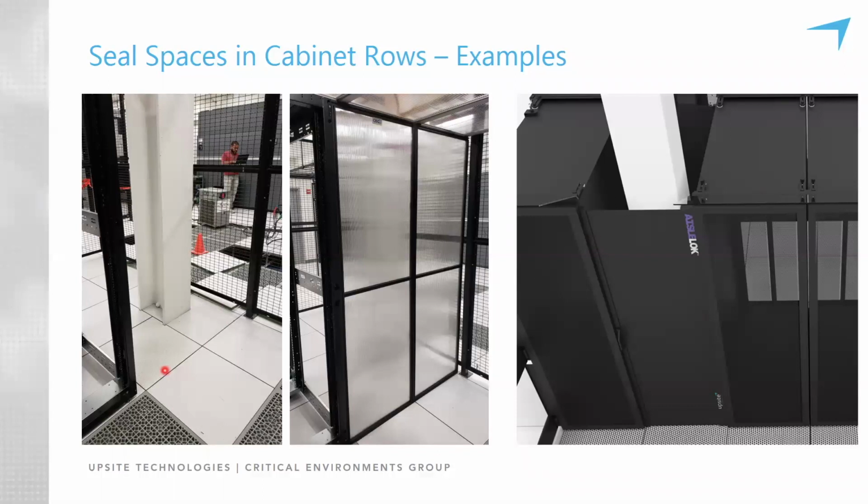You can see a very large building support column there between the end of a rack. This is a new deployment, so there hasn't been any hardware put in. It's actually the perfect time to do containment projects. But there's 48 inches and a little bit between the edge of that rack and the cage, right? And so you've got the column there. You've got a 24-inch wide space and then the column.